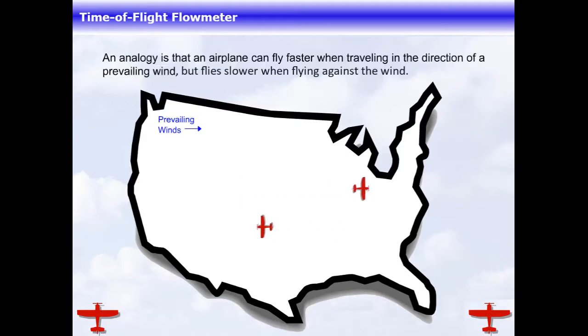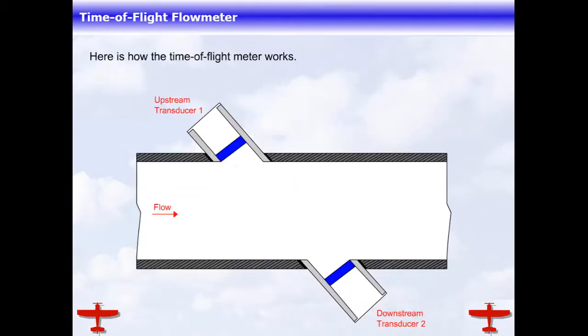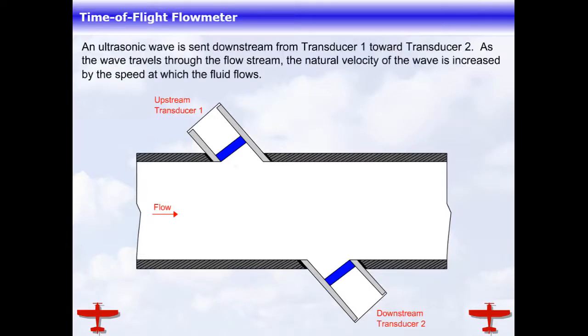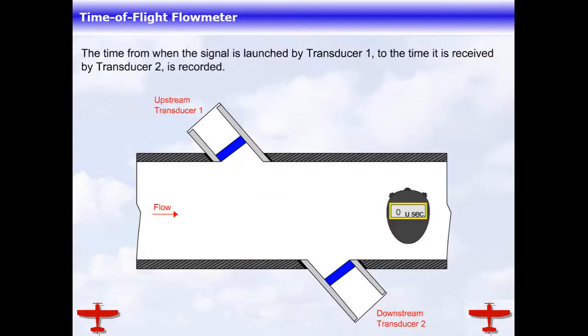An analogy is that an airplane can fly faster when traveling in the direction of a prevailing wind, but flies slower when flying against the wind. Here is how the time of flight meter works. An ultrasonic wave is sent downstream from transducer 1 toward transducer 2. As the wave travels through the flow stream, the natural velocity of the wave is increased by the speed at which the fluid flows. The time from when the signal is launched by transducer 1 to the time it is received by transducer 2 is recorded.